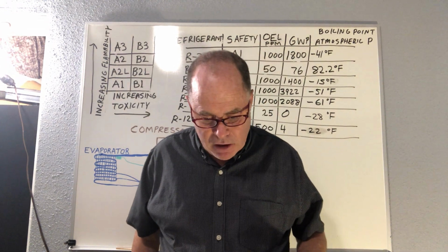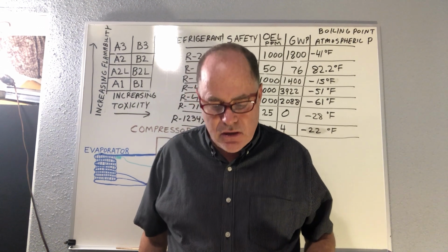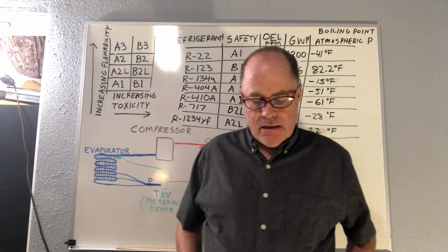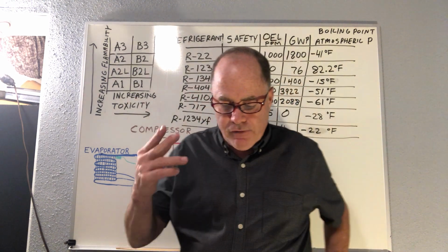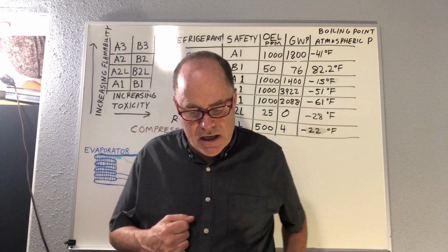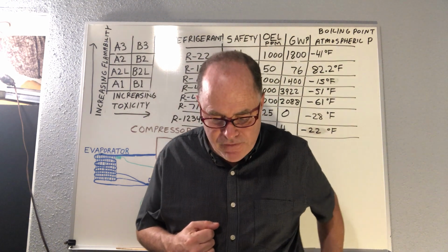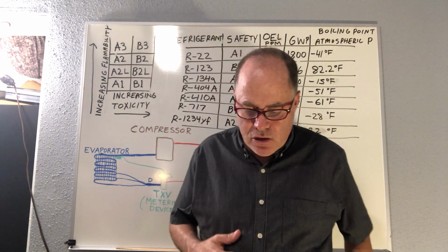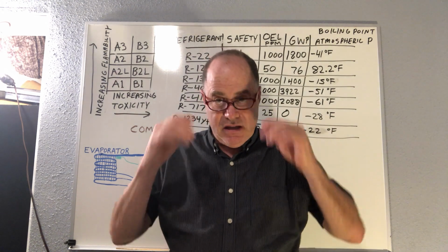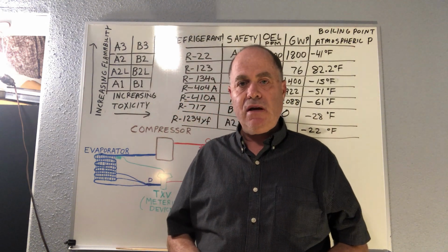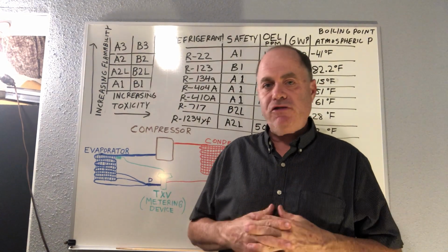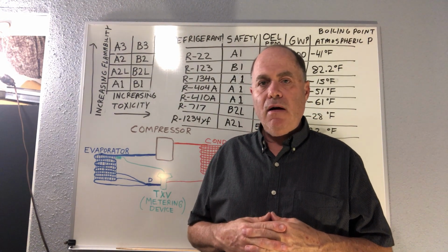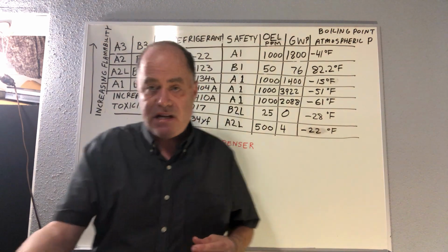And let's move on. It says here under quantity in 1105.12.1, the amount of refrigerant stored in a machinery room in containers not provided with relief valves and piping in accordance shall be not to exceed 330 pounds. Okay. There's some buildings and some companies, particularly like grocery stores, supermarkets, that will store up to 11 of these.